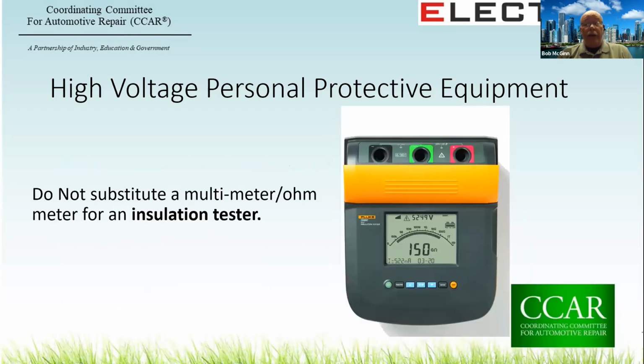And as we wind down here, just because NHTSA demands 500 ohms per volt system isolation doesn't mean that you don't need an insulation tester. If you were going to be testing insulation, you can't do it with a multimeter. An insulation tester uses a reference voltage anywhere from 500 to 15,000 volts DC. And if you're looking at the illustration of that Fluke that's up on the screen, it's showing 150 gigaohms at 5,249 volts reference.